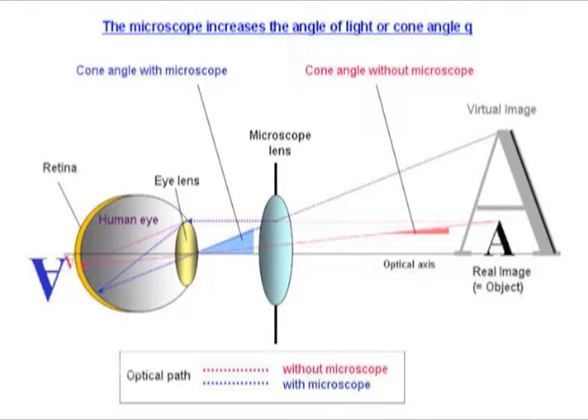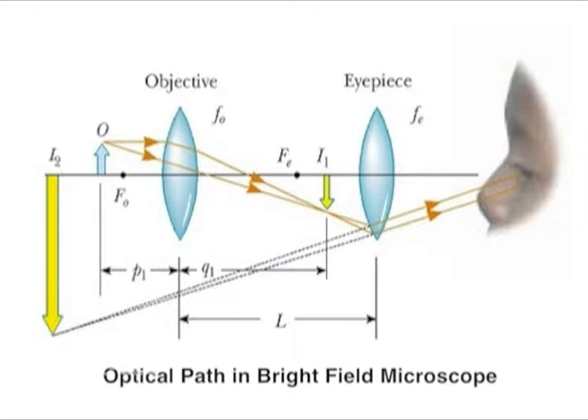The most critical feature is the correct adjustment of the condenser lens. When a microscope is used at high magnification, the condenser is usually placed such that it provides collimated illumination, in which the specimen is illuminated by parallel rays of light. In a compound microscope, magnification is achieved when light rays from the illuminator pass through the condenser, which directs the light rays through the specimen. The light rays then pass into the objective lens, which is closest to the specimen. The image of the specimen is again magnified by the ocular lens or eyepiece.